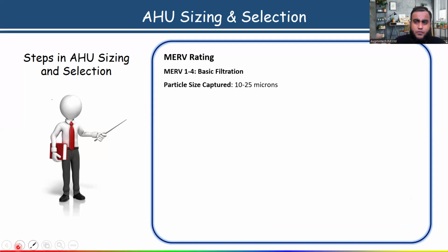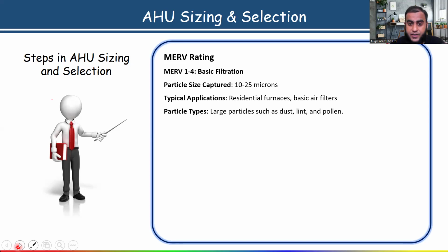MERV ranges from 1 to 16, I think. MERV 1 to 4 is the basic filtration, and it can capture 10 to 25 micron particle size. Where do we use this type of filter, MERV rating 1 to 4? Residential furnaces, basic air filters. The particle type is large particles such as dust, lint, and pollen. So they can filter these large particles. Is it clear? Tell me, please.